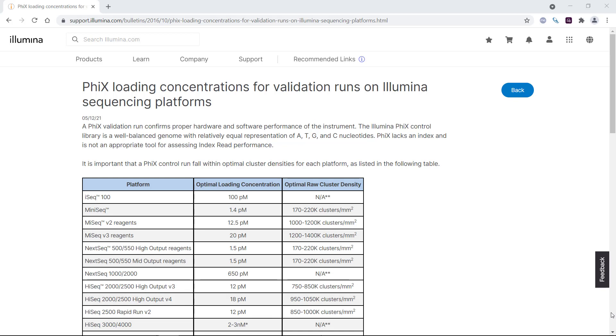If guidance is not found in either the library prep kit or sequencing platform documentation, we can choose a starting concentration based on the library size in relation to Illumina's PhiX control. Here I'm looking at a technical bulletin that outlines platform-specific loading concentrations for a PhiX run, also known as a validation run.